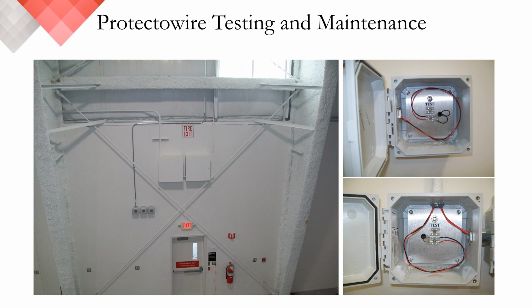Here we see the junction box is located a couple feet above the exit. In this example, testing of the 3 zones is done from this one location by simply shorting the detector. The use of a restorable, fixed temperature device, like a spot heat detector, would require each detector be tested with a heat source individually per NFPA guidelines. This would require a scissor lift, removal of any aircraft, and a few days' time. Considering linear heat in areas and applications like this will ultimately save you time and money on both your installation and annual testing.